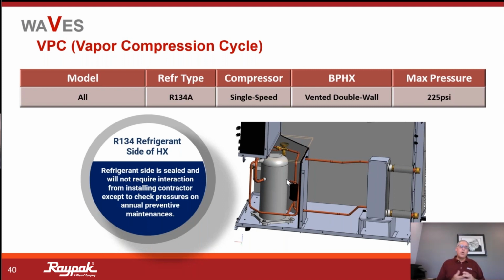Now, down the road, when you do our level 3 for startup and commissioning, maintenance, and troubleshooting, I will show a couple of slides on the programming where we can go in and check what those pressures are, if they're adequate, or rather if the refrigerant is at the necessary charge levels that it should be at. So more to follow on that, but this really does add a comfort level to mechanical contractors and plumbing contractors knowing that they do not have to interact with that refrigerant process because they might not be licensed in that, right? So this is a big factor that we want to talk about.